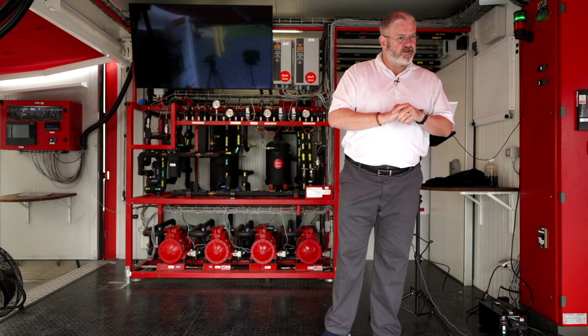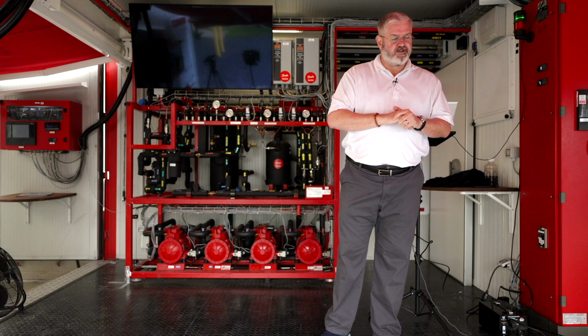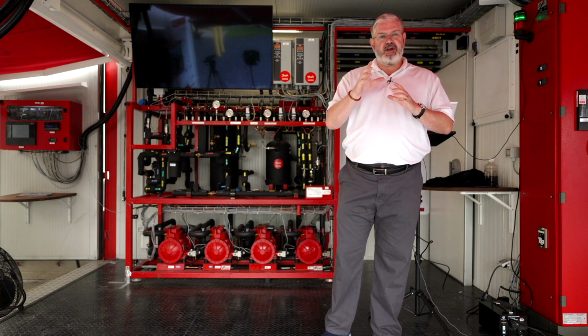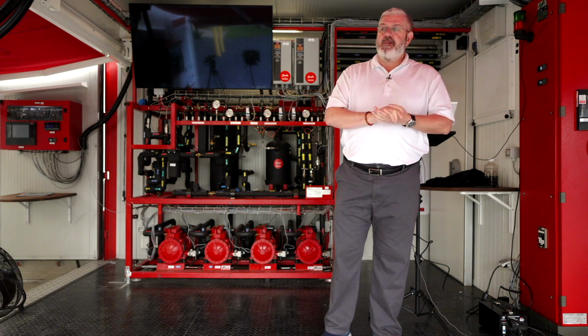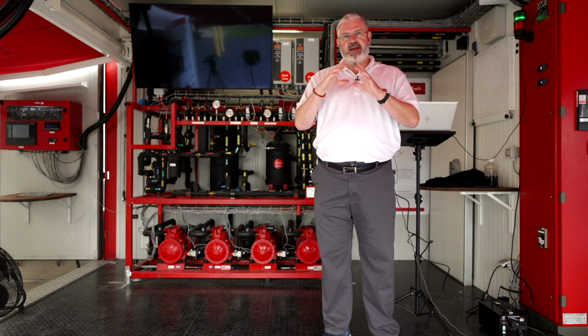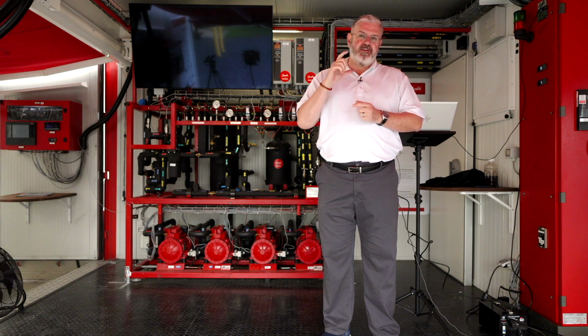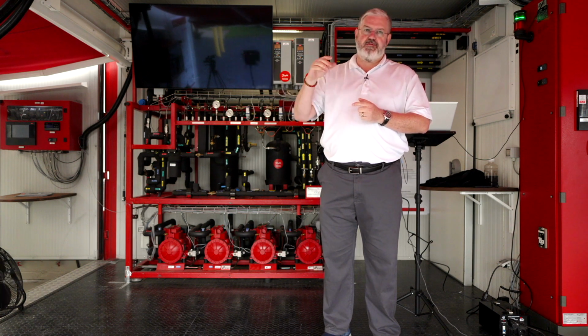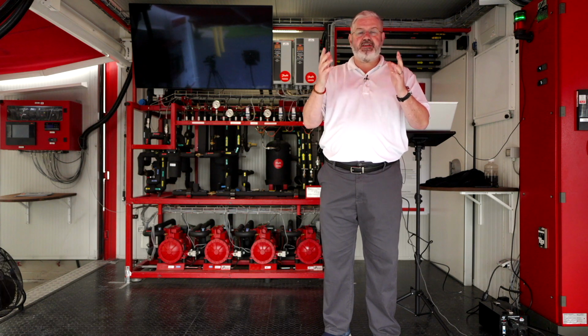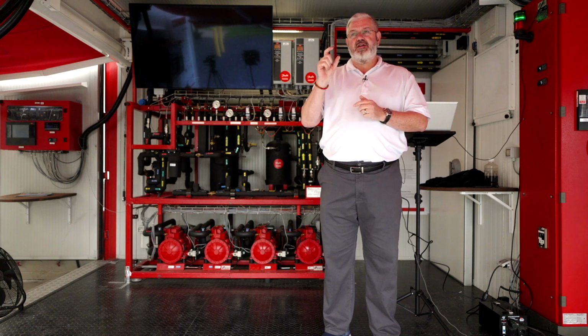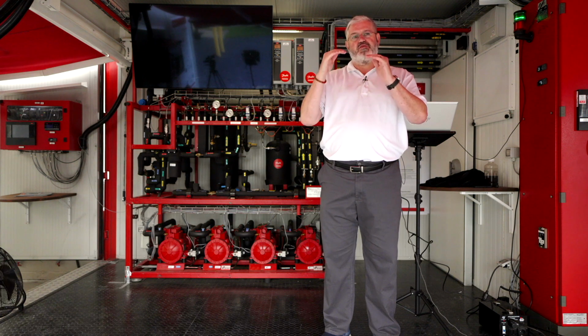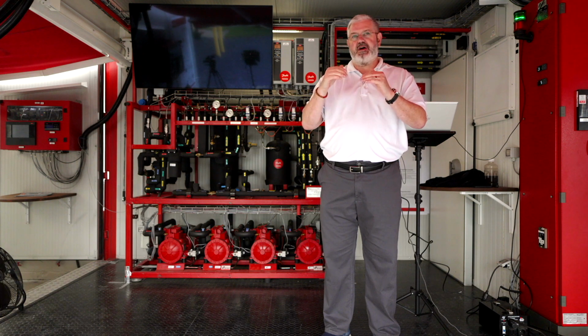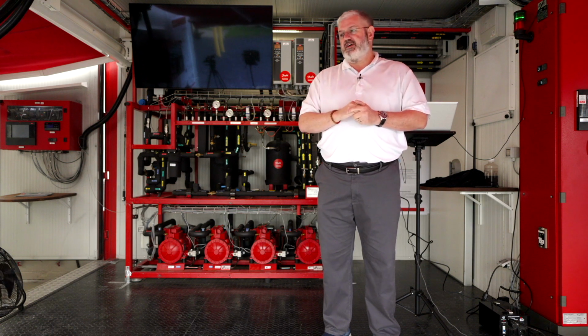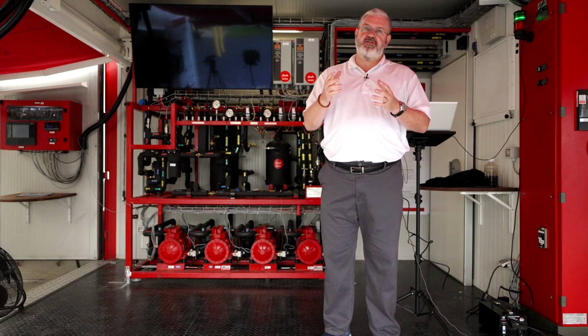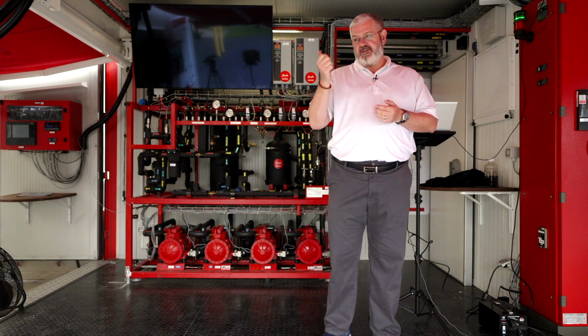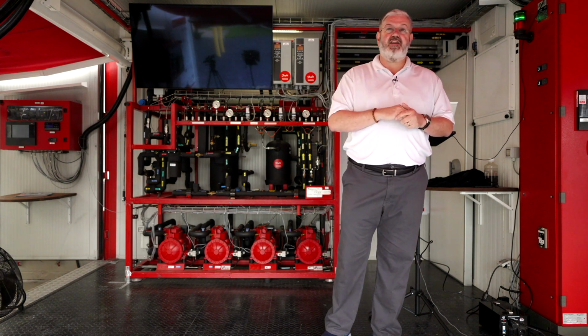Excuse me, how does the controller determine capacity required from ejectors? So it's basically defined. That's a great question. I had never had anyone ask that. So it's defined within the controller, not unlike condenser fan banks. You select a model for the ejector. I think the one on the table over here is an HP high pressure 1875. When you select that model, it knows what ejectors go in that, and it'll predefine the various capacities of the ejector blocks based on the model entered in the software. So in theory, you could have some control issues with an ejector block. Might want to check the model on the ejector block itself and verify that's what's defined in the pack controller.